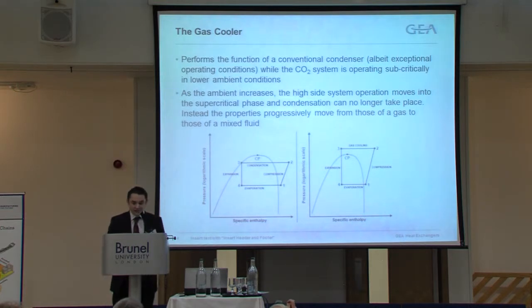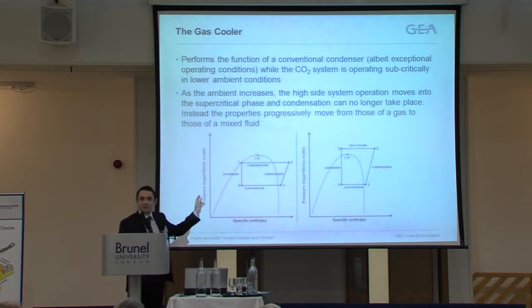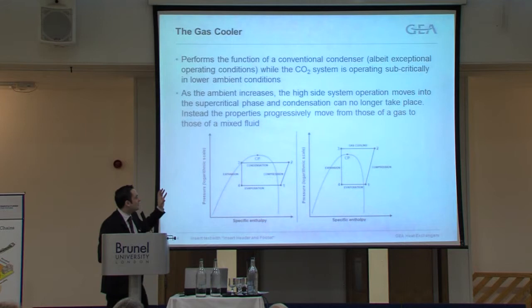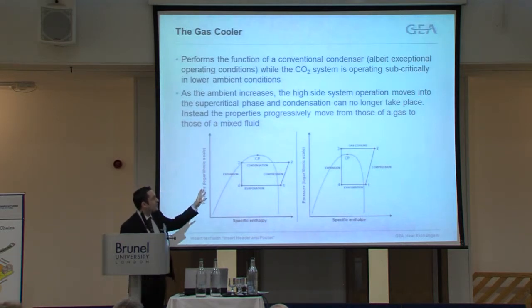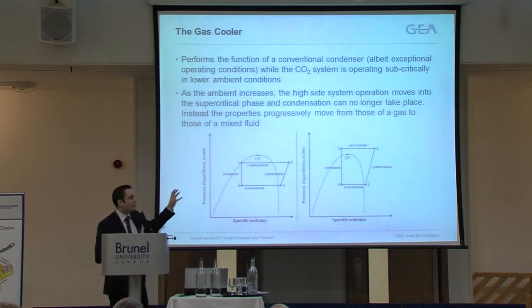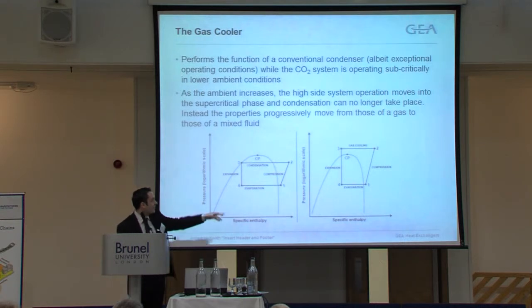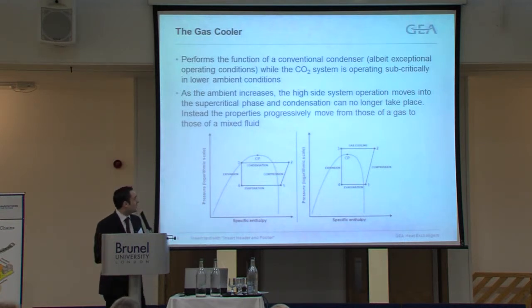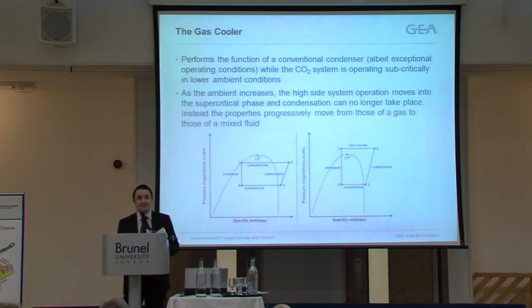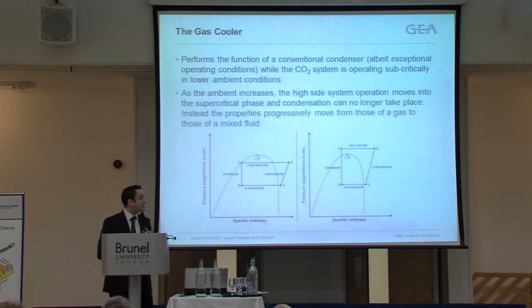Okay, so very quickly, what is a gas cooler? It performs the function of a condenser when the ambients are low, approximately 24-25 degrees C. As the ambient temperature increases, it pushes the fluid into the supercritical phase. So condensation is no longer possible when you get to the supercritical phase, as can be seen in the pressure enthalpy diagram on the left there. And therefore, the fluid goes in as a gas, it's discharged from the compressor as a gas, and the fluid properties progressively change, and it leaves as a mixed fluid, if you like.